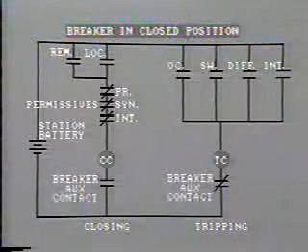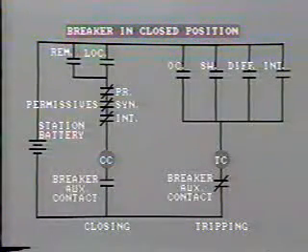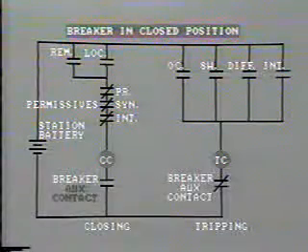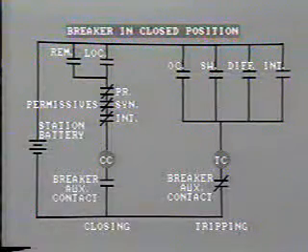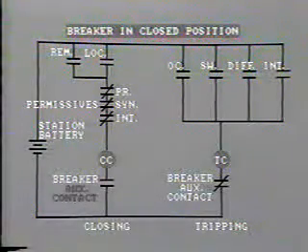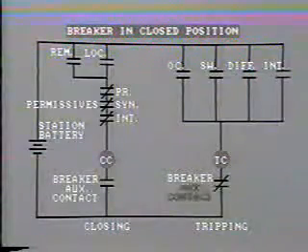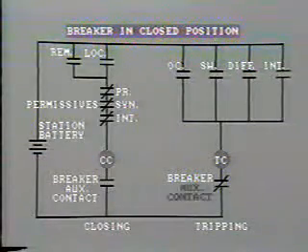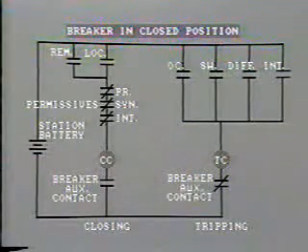How is this achieved? When the breaker is firmly closed, it mechanically actuates auxiliary contacts in the control circuit. It opens the auxiliary contacts here, de-energizing the closing circuit. At the same time, it will close these auxiliary contacts in the tripping circuit, so enabling this circuit to operate when required.